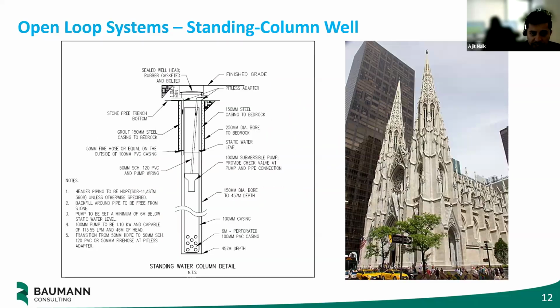There's another kind of open loop system called a standing column well. This yields about 10 to 30 tons per well - it's the second most efficient. St. Patrick's Cathedral in Manhattan uses this type of system, where it's basically a sealed well that goes down, pumps up the water from underground, and uses it in the same way. It doesn't rely on an aquifer, and its pumps can be done in a little bit tighter formats, but it works well.